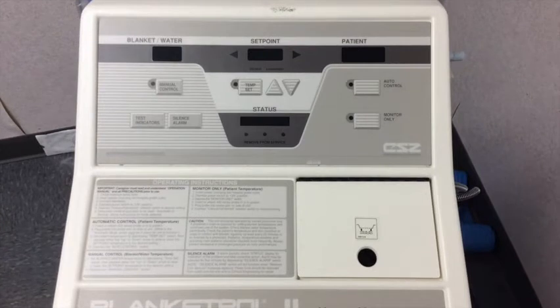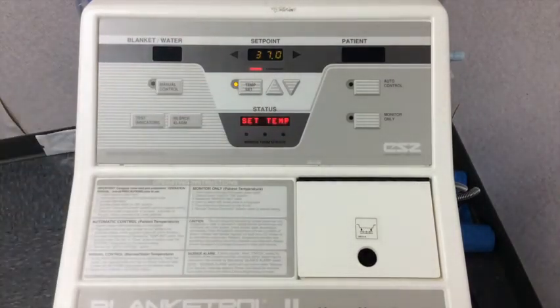Once the blanket is on the patient and therapy is ready to be initiated, everything is fairly straightforward. You'll utilize the on-off toggle switch on the front to turn the machine on. The machine's then going to prompt you to set your temperature set point. You'll choose temperature set. Typically it's going to default to 37 degrees Celsius or 98.6, which is typically what we think of as being normothermic for a patient. You have three different modes you can choose from.